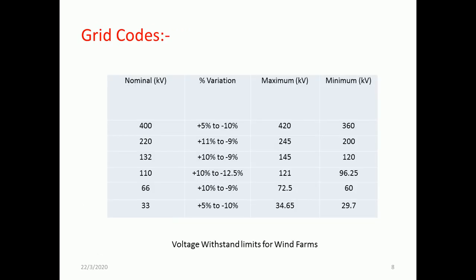Now, what are the grid codes with respect to the voltage withstand for various wind farms? If you see the table, the voltage levels are listed here, along with the percentage variations, which say what voltage variation is permissible. The maximum and minimum voltage variation is also discussed. If we speak about a 132 kilovolt system, the permissible voltage variation is plus 10% and minus 9%. The permissible limit is a maximum of 145 kV and a minimum of 120 kV. These grid codes for voltage requirements are to be maintained.